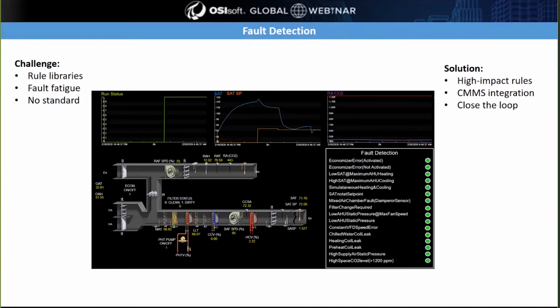Then the sort of inverse of that is if you've got an outside air damper that's 100% closed, then maybe that's a safety issue because there's no ventilation, and that can all be handled with a couple of targeted analytics at the economizer operation. The next one I would want included in all fault detection systems would be simultaneous heating and cooling. Again, it wastes a lot of energy and reduces the overall capacity of your system.